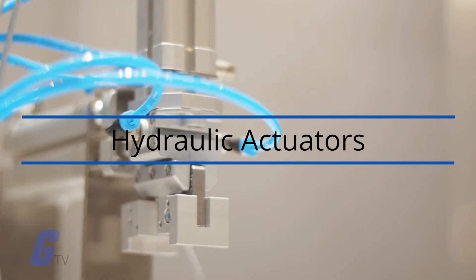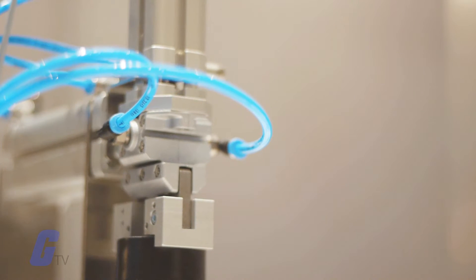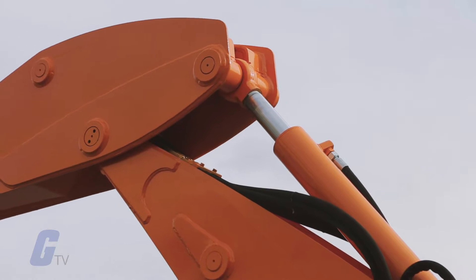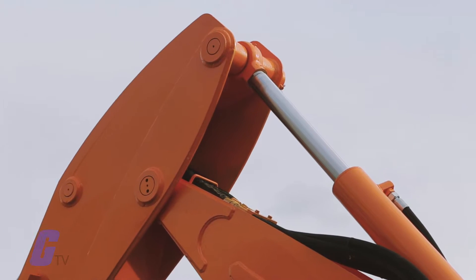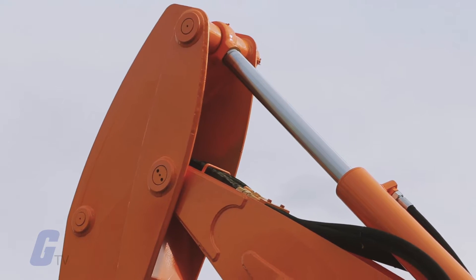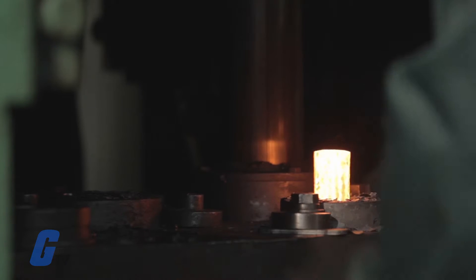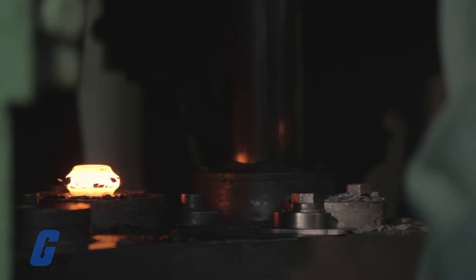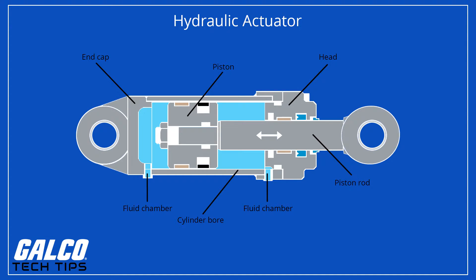Hydraulic actuators, as used in industrial process control, employ hydraulic pressure to drive an output member. These are used where high speed and large forces are required. The fluid used in hydraulic actuators is highly incompressible, so that pressure applied can be transmitted instantaneously to the member attached to it. A hydraulic actuator consists of a cylinder or fluid motor that uses hydraulic power to facilitate mechanical operation.